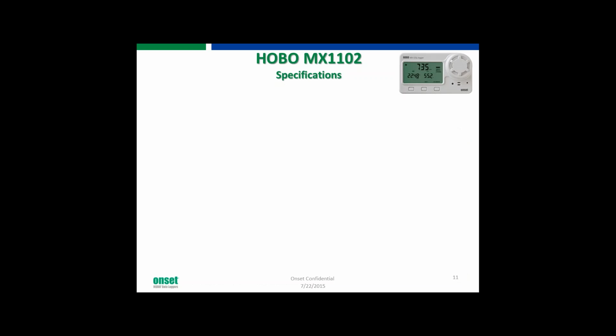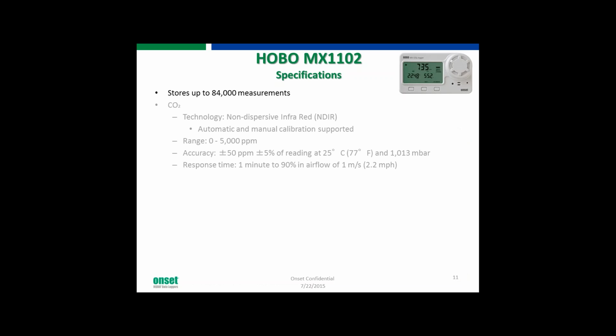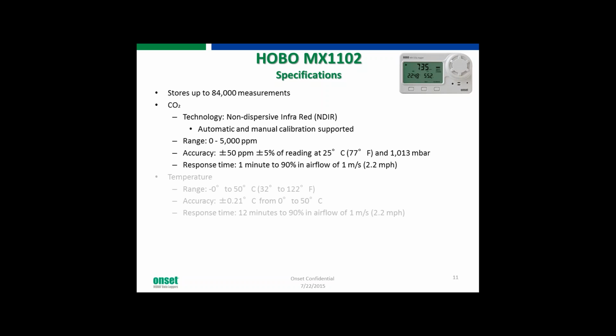Quick discussion of specs. Basically, this has the same amount of memory as the MX1101 product, if you're familiar with that: 84,000 measurements, or 128K. The CO2 sensor uses a technology called non-dispersive infrared absorption technology. We're going to talk about that in a moment. It does support both automatic and manual calibration. We're going to talk about that also. The range is 0 to 5,000 ppm. The accuracy is plus or minus 50 ppm, plus or minus 5% of reading. Our response time is about a minute.